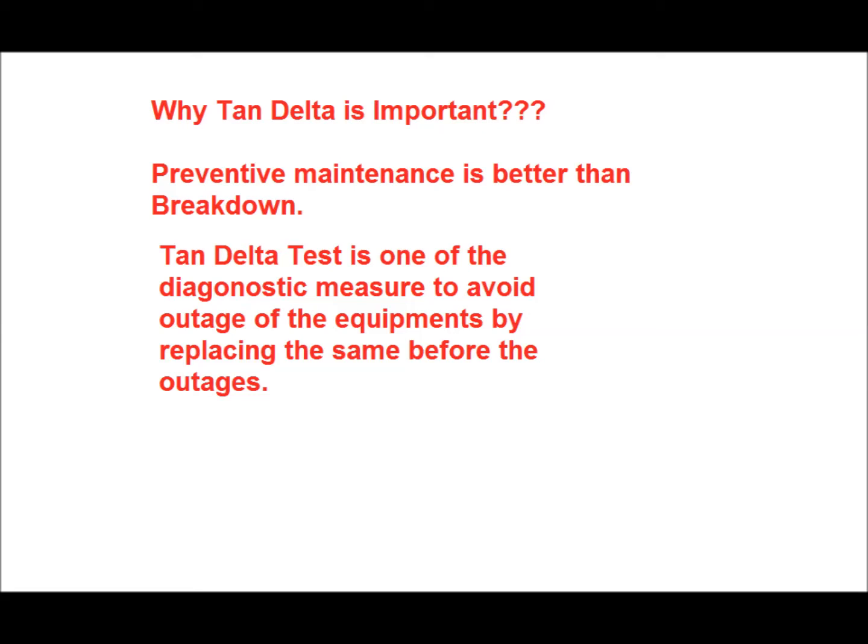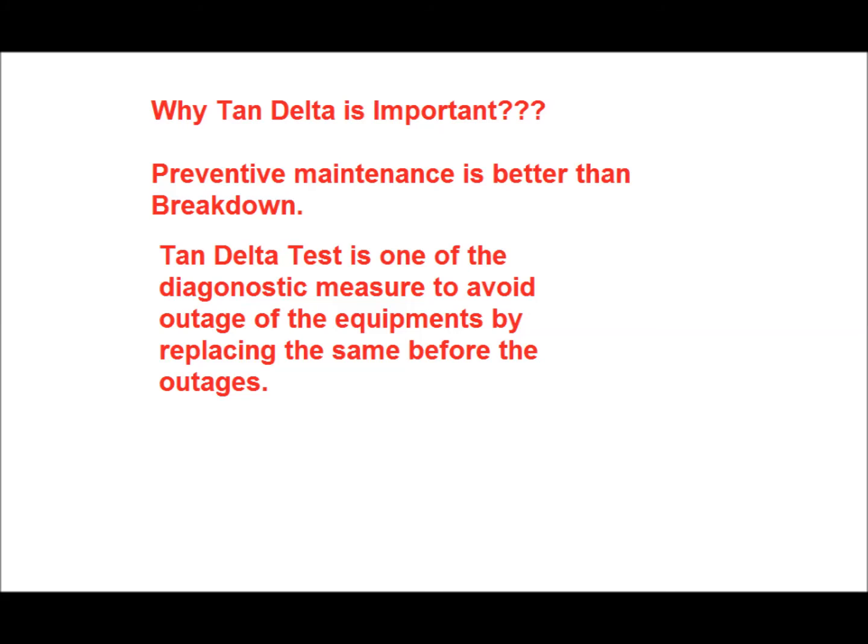Tan delta is a direct indication of power dissipated through the insulation and is a very important measure for the quality of insulation. Variation of tan delta with applied voltage gives a clear indication of the presence of any impurities, imperfections, or voids in the insulating material, and serves as an early indication of failure hazard — meaning the equipment should be replaced as soon as possible.